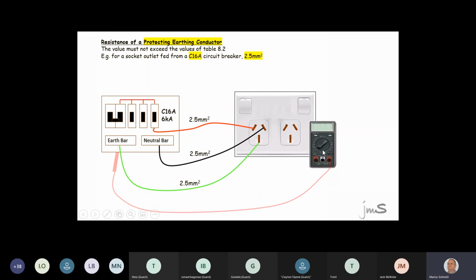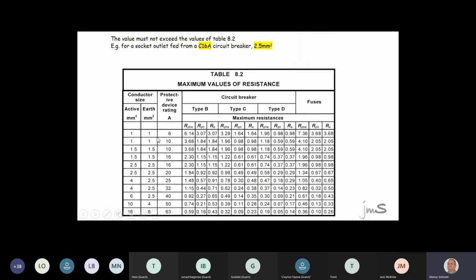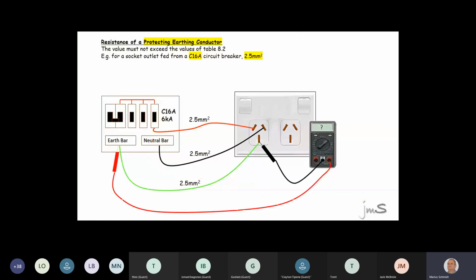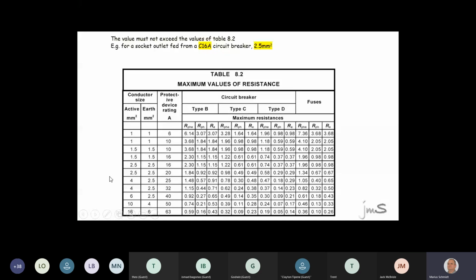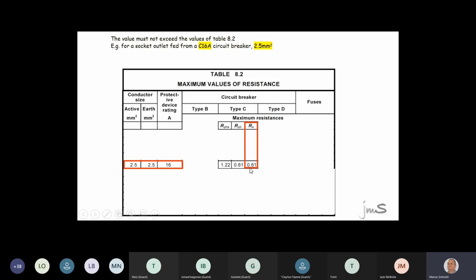Right, you take your ohm meter, you measure between earth and earth, and you're going to measure between phase and phase. Got it? And the resistance of earth and earth, phase and phase, must be less than table 8.2. Now, it is very important that your phase and your earth is less than those 2 values. Or alternatively, together, less than 1.22. But when you do this test, and if it is, then you know your impedance test is okay.